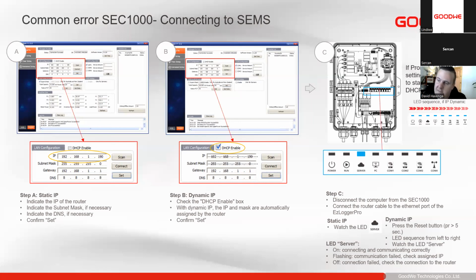That reset button. So we'll press and hold the reset button for about 5 seconds, let go. We should see the LEDs cycle from left to right. If this doesn't happen, try it again. If it still doesn't happen, then press and hold it for 10 seconds. Then we'll see the right to left, and then press and hold it again for a short period of time, and then we'll see the left to right. Then we'll be in DHCP. We can plug it into the customer's network, and we should see after a few seconds that the server LED will then go on steady.